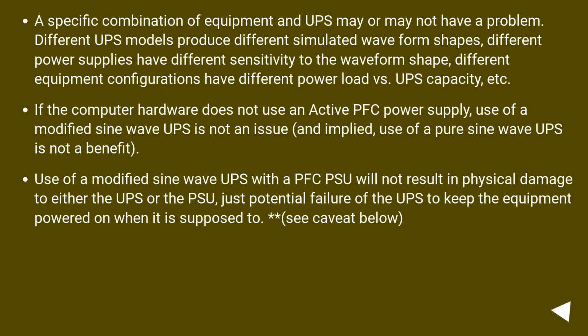If the computer hardware does not use an active PFC power supply, use of a modified sine wave UPS is not an issue, and use of a pure sine wave UPS is not a benefit. Use of a modified sine wave UPS with a PFC PSU will not result in physical damage to either the UPS or the PSU, just potential failure of the UPS to keep the equipment powered on when it is supposed to. See caveat below.